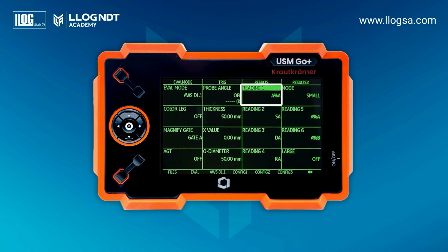At the top, we have the readings available in the A-scan bar: echo height or amplitude in gate A, sound path or distance, difference between A and B gate paths, depth, projection or surface distance, reduced projection, which applies if the X value was entered, and the leg number. The same readings can be configured for gate B.